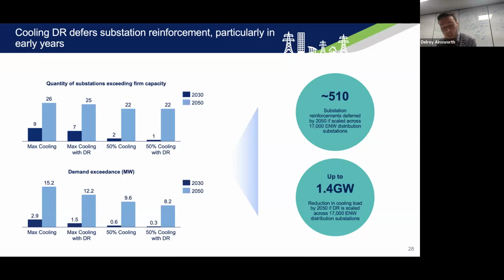If we then scale that across ENW's network, this could defer 510 substation reinforcements by 2050 and produce a 1.4 gigawatt reduction in cooling load via DR. And just to add to that, we only scaled up across ground-mounted substations for this project, so those projected numbers would likely be higher with PMTs included. Next slide, please.